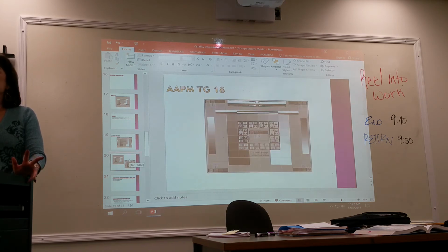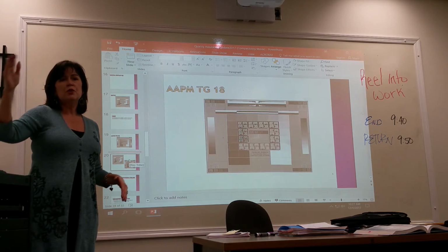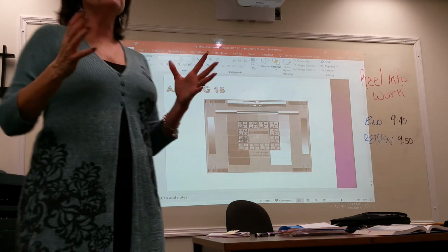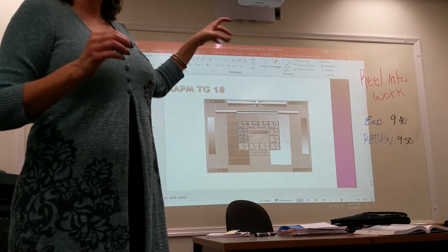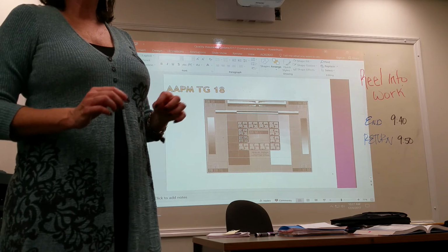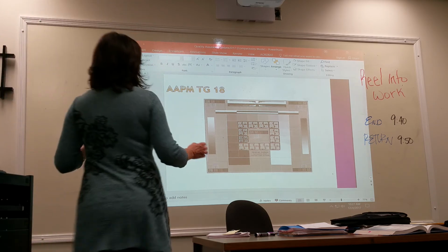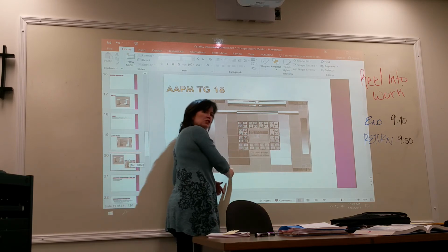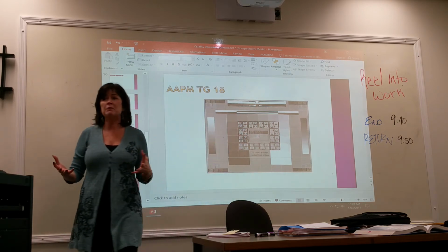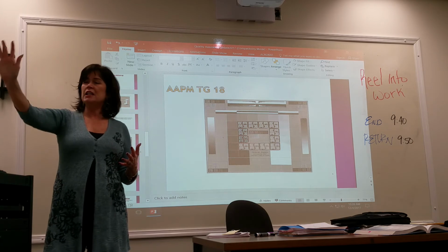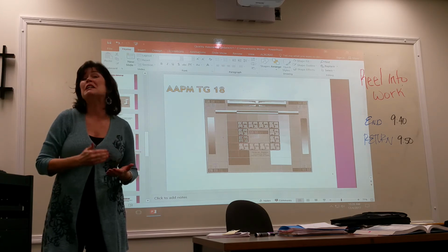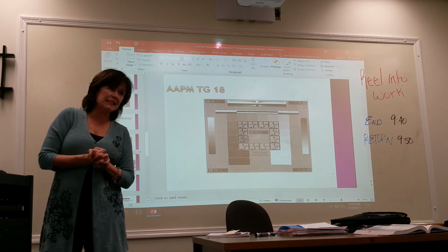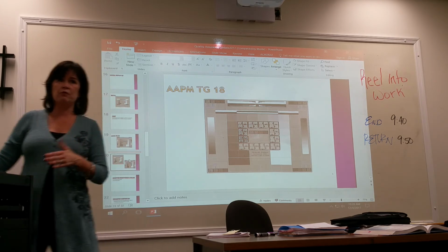So what does it mean? It means nothing to us, but when you're performing your test of the monitor, whatever the criteria is that you're supposed to look at, you're supposed to be able to see this pattern clearly, you're supposed to be able to see this many shades of gray, whatever the criteria may be, when you see that pattern, each and every time it comes up, it needs to be what? The same? The same. It needs to be consistent. Okay, so that's what we're looking for, consistency.